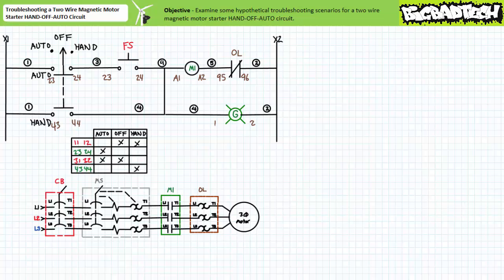It might be better to run a wire directly from the 4-4 terminal of the selector switch hand contact to the A1 terminal of the M1 contactor coil, and another entirely separate wire from the 2-4 terminal of the simulated float switch to the A1 terminal of the M1 contactor coil, for reasons of robustness and reliability. This way, in the event the wire to the contactor coil is severed from the logic in rung 1, rung 2 is there to bypass the automatic input. Similarly, in the event the wire to the contactor coil is severed from the logic in rung 2, rung 1 is there to automatically govern the system.